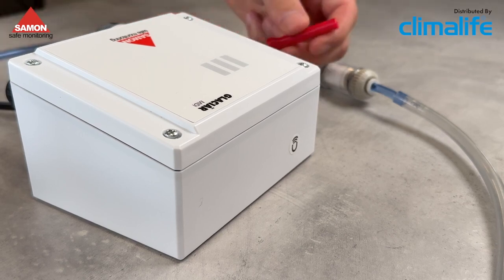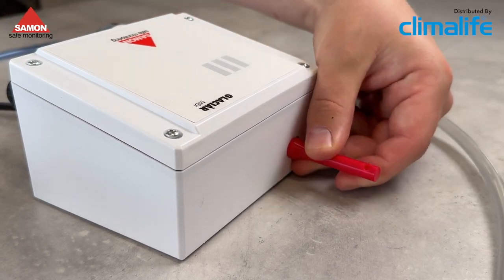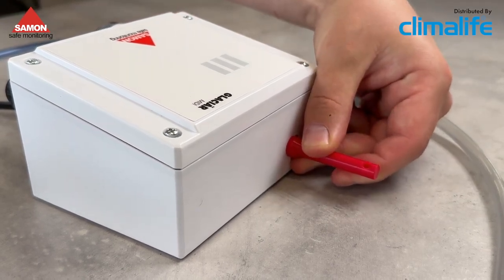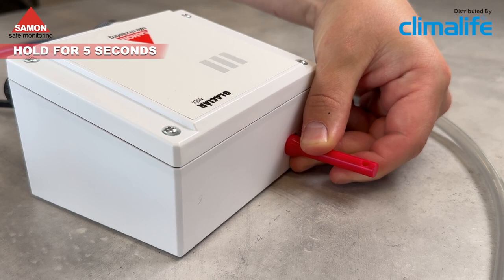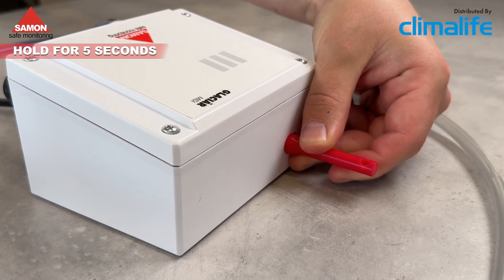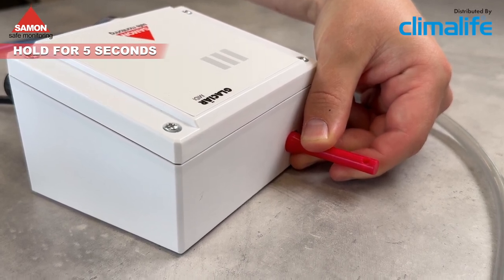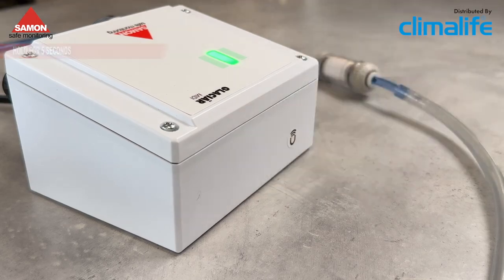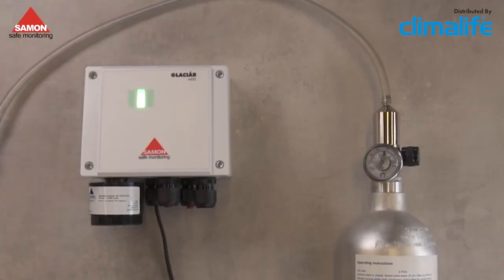Finally, make sure the gas detector is no longer in service mode. This is done by holding the magnetic wand on the marked spot on the top of the unit for 5 seconds. When the green LED light is turned on and not flashing any longer, the unit is back in operating mode.